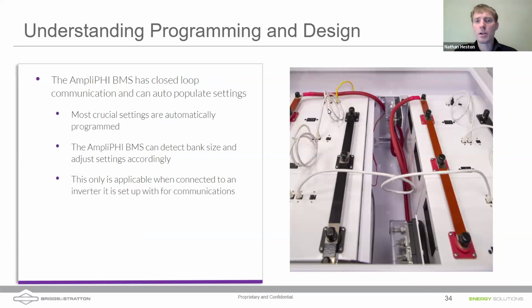What's shown here is connecting properly the closed loop communications, one big loop, all 6 of these batteries. It's also showing the combining of these batteries. You can see we're pulling power off of opposite corners of the battery stacks, and we have these two battery stacks in parallel. We never run our batteries in series. It's important that we keep our batteries balanced, both with the external connecting equipment as well as the BMS units inside doing that.